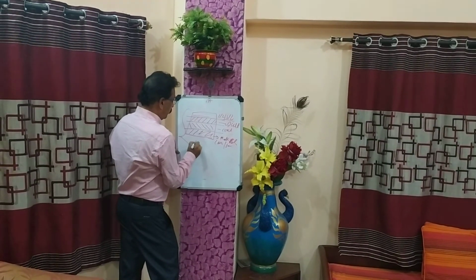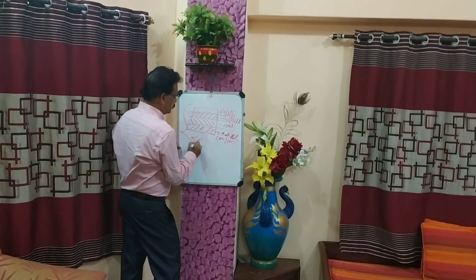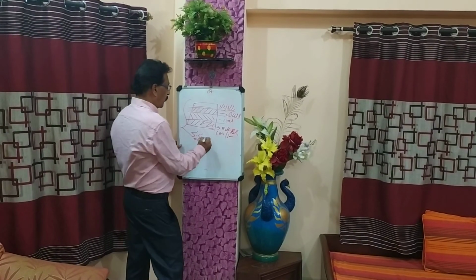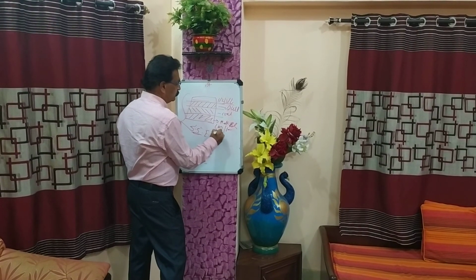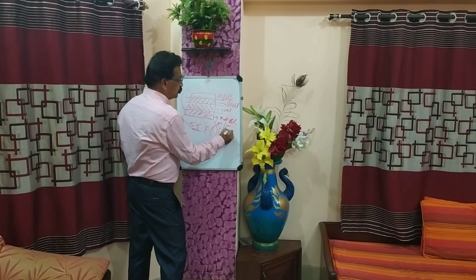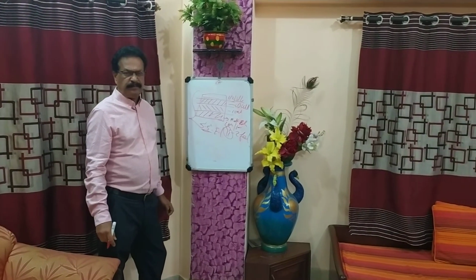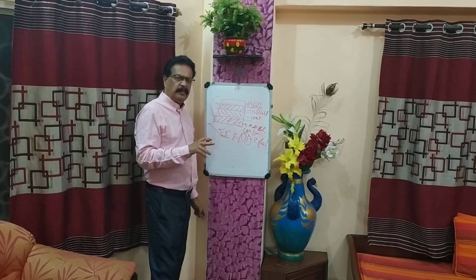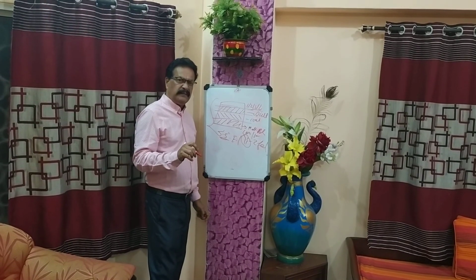The depth should be 5 foot 5 inches - depth of the pit of the earth. It should have 2 funnels to pour the water in. At least every 2 months, one time you have to pour the water. If the soil is wet, then it's okay.